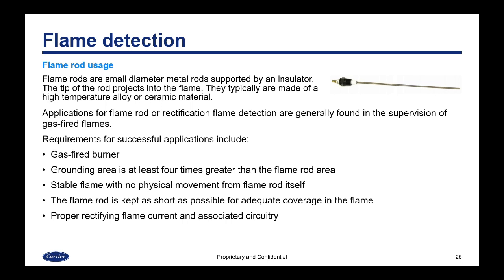Flame rods are small diameter metal rods supported by an insulator, with the tip of the rod projecting into the flame. They are typically made of a high temperature alloy or ceramic material. Applications for flame rod or rectification flame detection are generally found in the supervision of gas-fired flames. Requirements for successful applications typically include that it's a gas-fired burner, the grounding area is at least four times greater than the flame rod area, a stable flame with no physical movement from the flame rod itself, the flame rod is kept as short as possible for adequate coverage, and proper rectifying flame current and associated circuitry are provided.